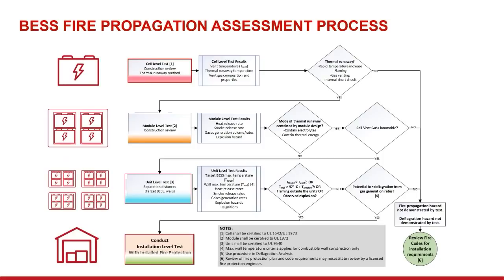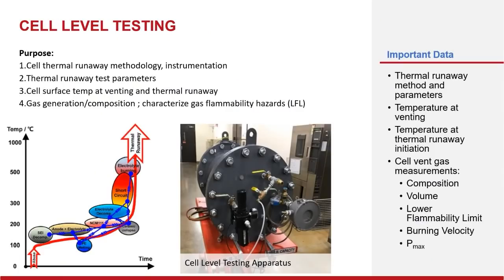This was a flow chart created by the research team here at UL to give a guideline on how to follow 9540A. It shows the cell level and the results of that cell level, if it will go to runaway, which can apply to any type of technology in the batteries, and it does, but we're specific here to lithium ion. If you realize thermal runaway in those cell level tests, we're going to go to the module level and then so on. So what are we evaluating at the cell level testing?